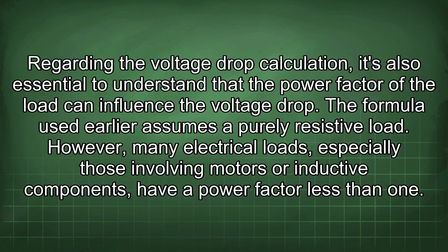Regarding the voltage drop calculation, it's also essential to understand that the power factor of the load can influence the voltage drop. The formula used earlier assumes a purely resistive load. However, many electrical loads, especially those involving motors or inductive components, have a power factor less than 1. A lower power factor means that the current is not perfectly in phase with the voltage, which can increase the voltage drop. For more accurate calculations in such cases, a more complex formula that considers the power factor should be used.